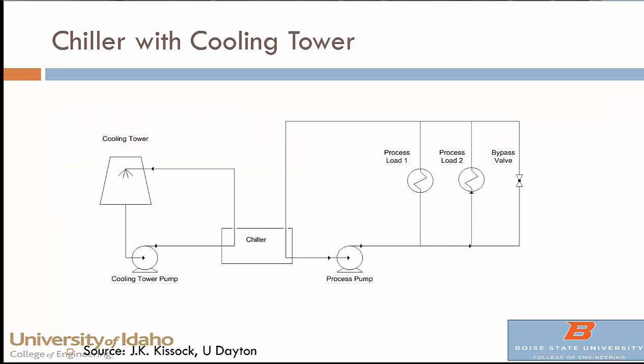In a typical industrial chiller arrangement, the chiller cools water that's used to take heat away from the processes — for example, chilling milk after pasteurization. On the other side of the chiller, heat is pumped to another working fluid that could use a rooftop cooling tower for evaporative heat rejection. What's not shown in these diagrams is that as some of this water evaporates, you need to add make-up water to compensate.